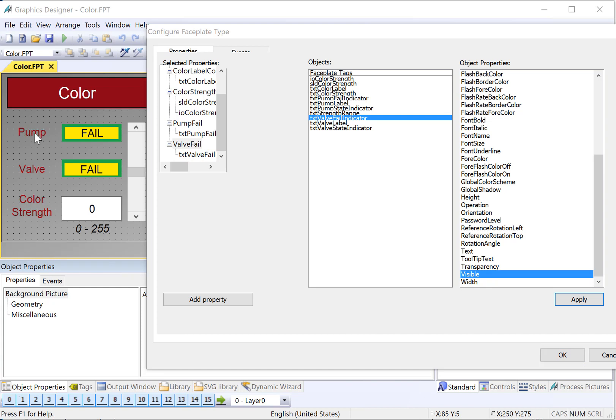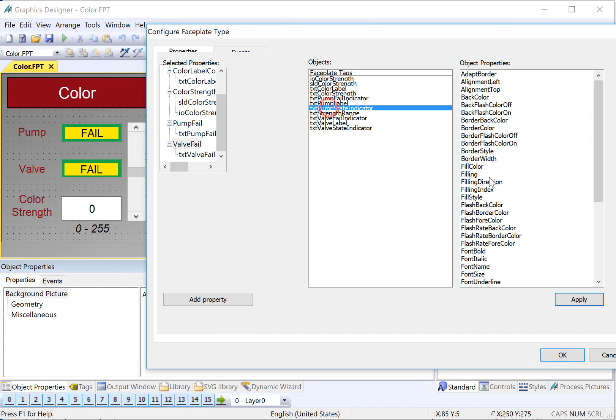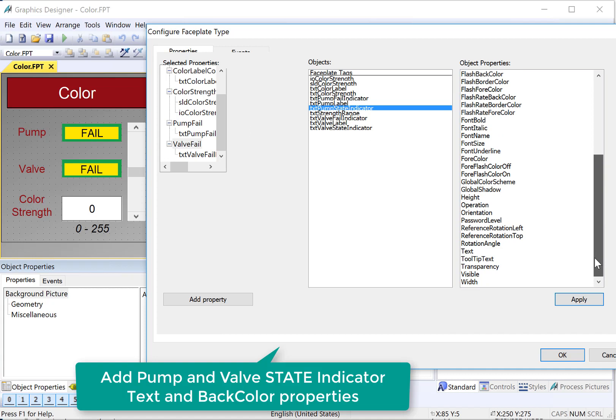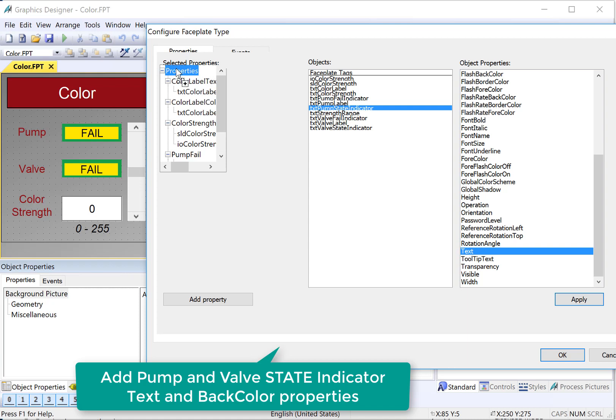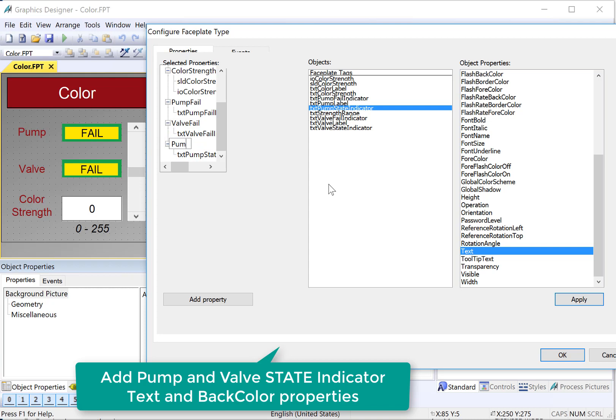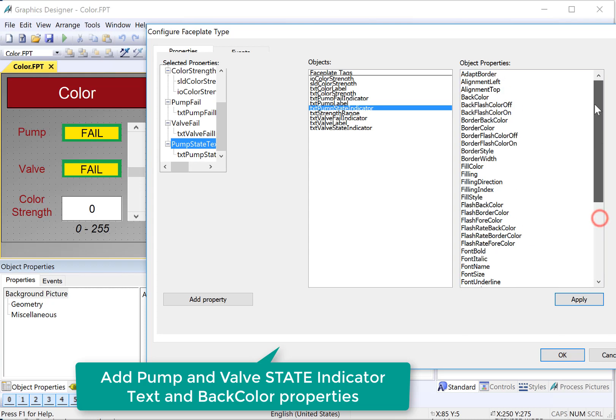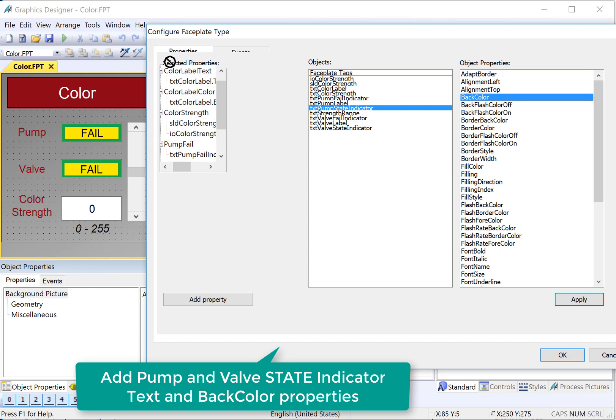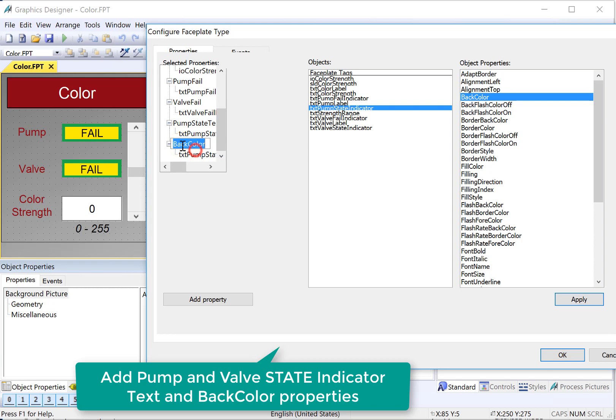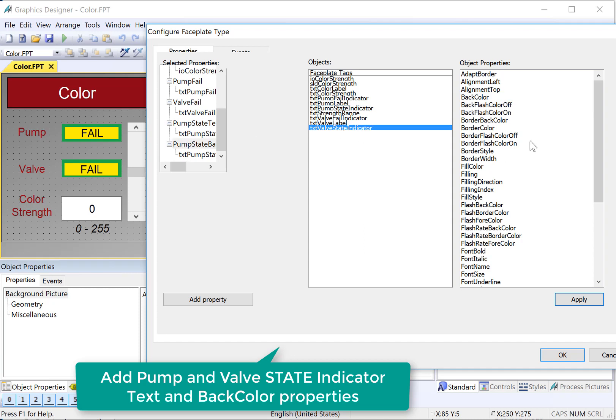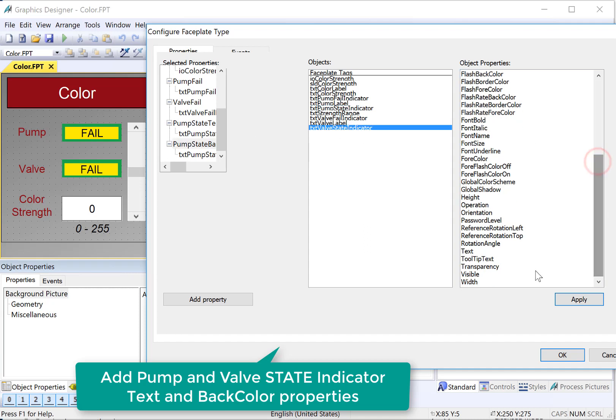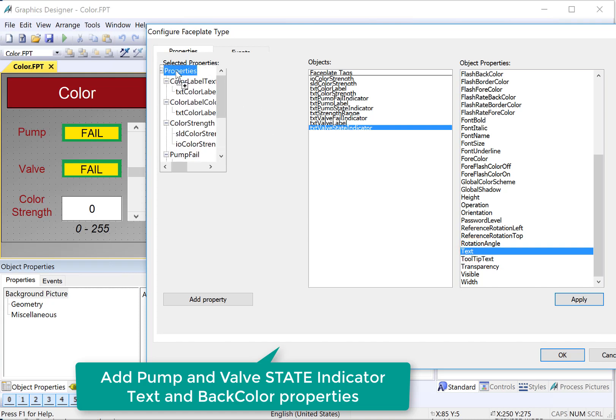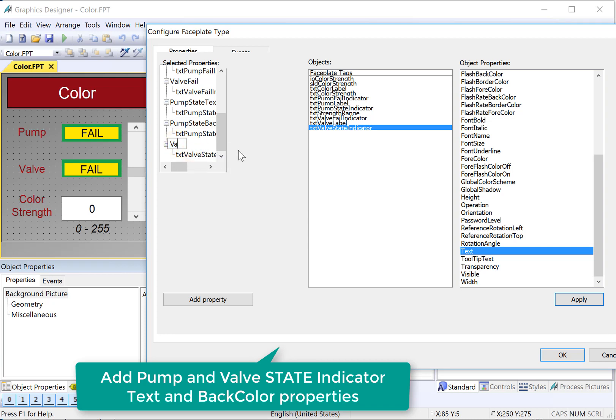We also need to do our pump status indicators, which are behind the fail. So we have our state indicator. And we need to be able to get to the text property of that to say if it's on or off. So I'll drop that under properties, rename, just call it pump state text. And then we would also need the color so that we could have it be red or green based on the color. So I'll grab back color, drop it under properties, rename it pump state back color. And then we'll do the same thing with valve. Here's our valve state rename, valve state text.